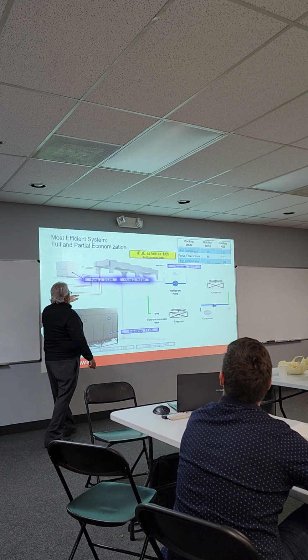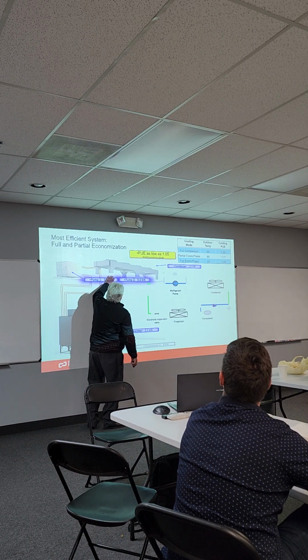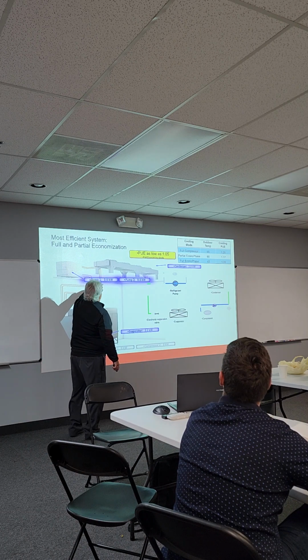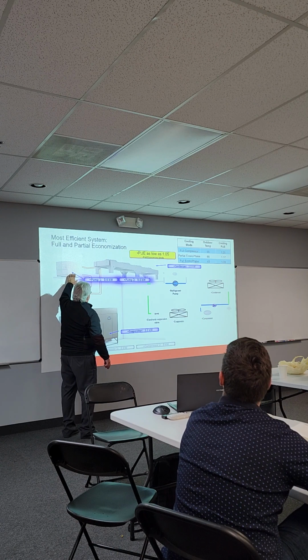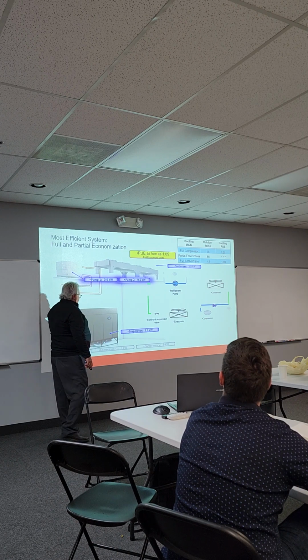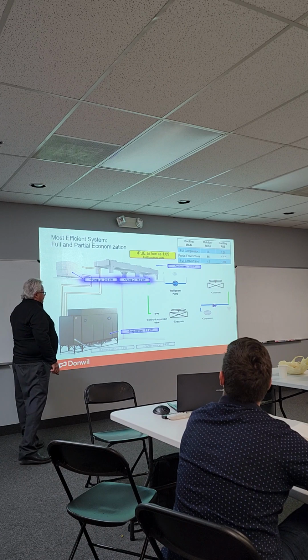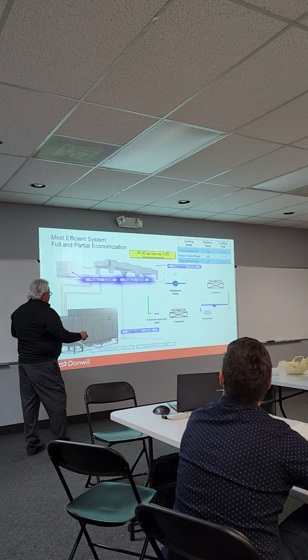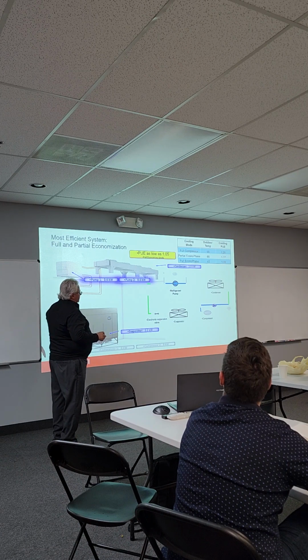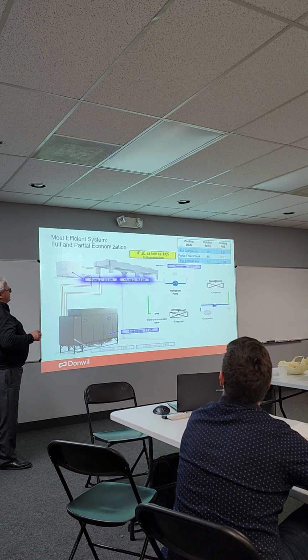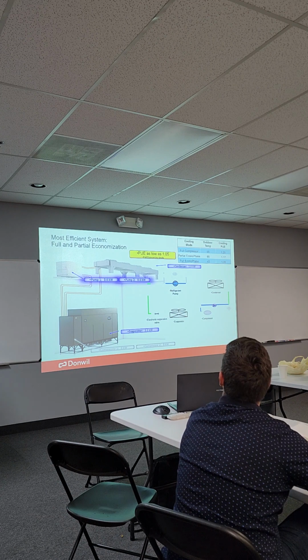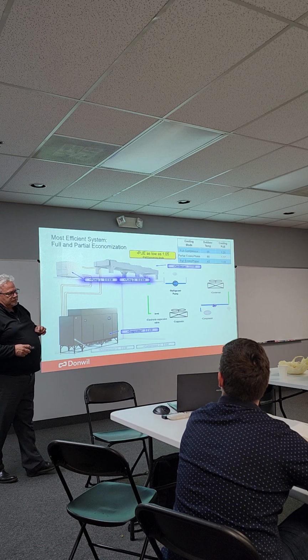So the condenser has to be elevated with at least like 36-inch legs, so that we have some fall coming to the pump, so we have liquid coming here, then liquid coming back down to your expansion valve. That's all controlled by electronic expansion valves. So you could see that this unit here, even though it costs a little bit more money because of the extra equipment that's built inside of it and the technology, has a payback of about 2 years.